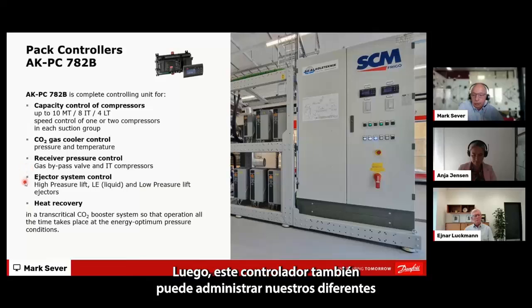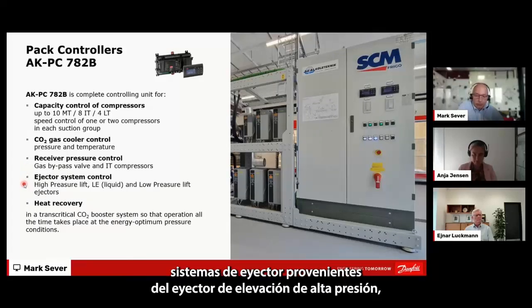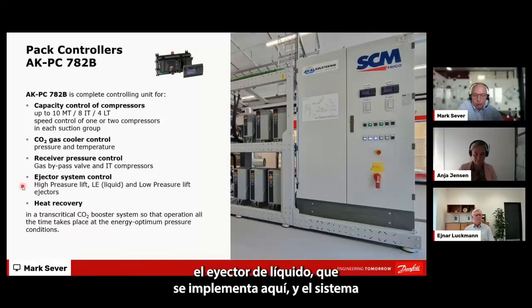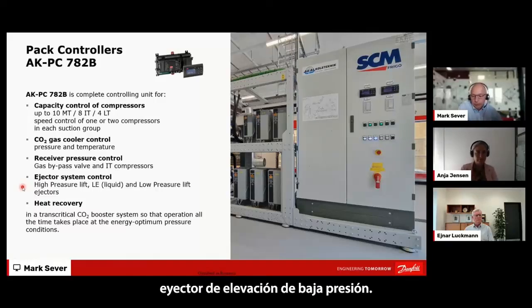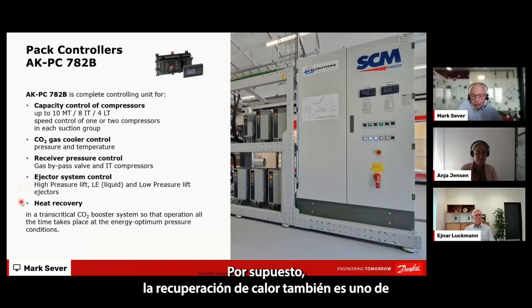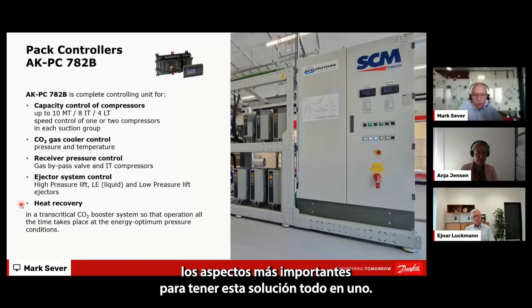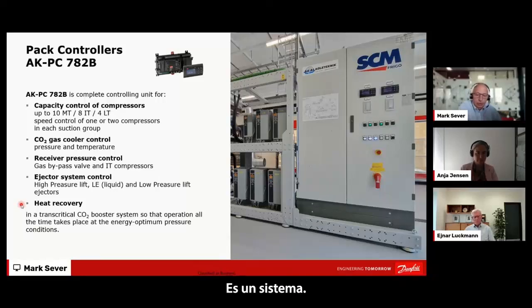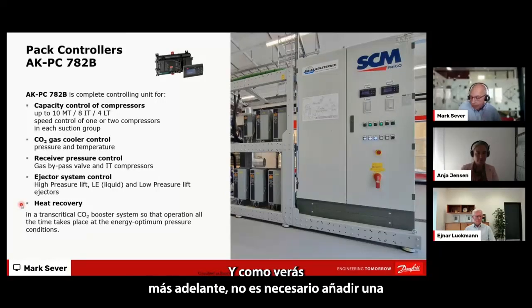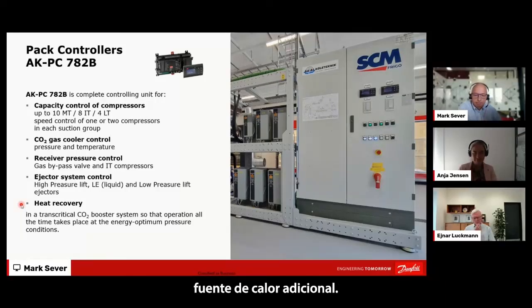This controller can also manage our different ejector systems, coming from high pressure lift ejector, liquid ejector, which is implemented here, and low pressure lift ejector system. Heat recovery is also quite important to have this all-in-one solution in one system, and as you will see later, it's not necessary to add any additional heat source.